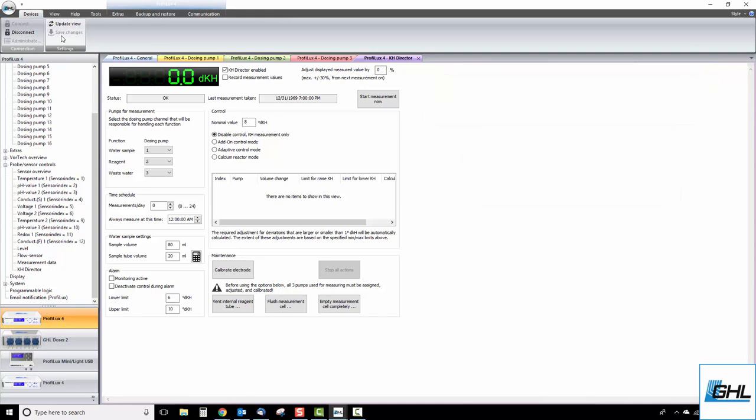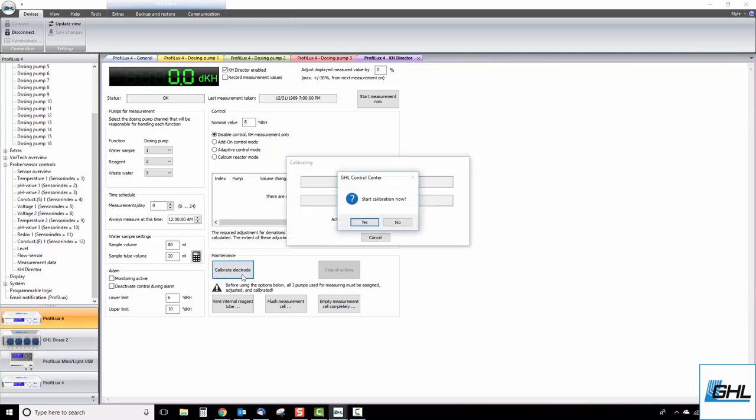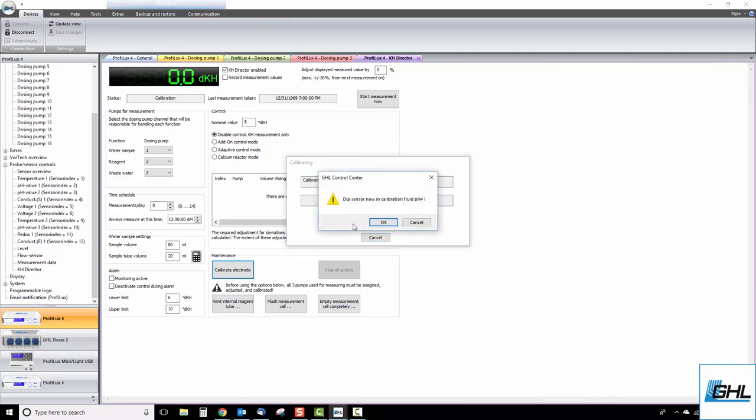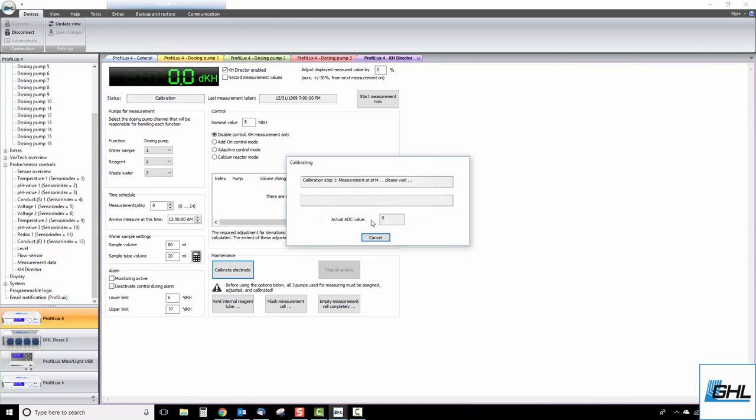To start the calibration, click on the button that says calibrate electrode and click yes to start. Take the KHD probe and let it sit in the sample of pH 4 fluid then click OK to begin calibrating with the pH 4 fluid. Give the probe a few minutes for this process to complete.